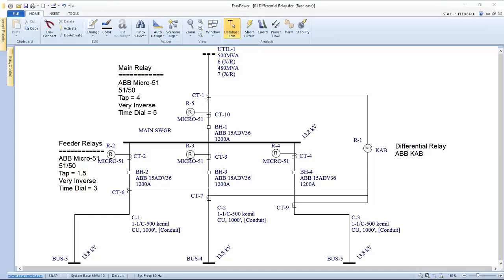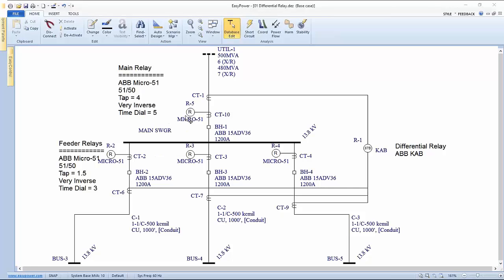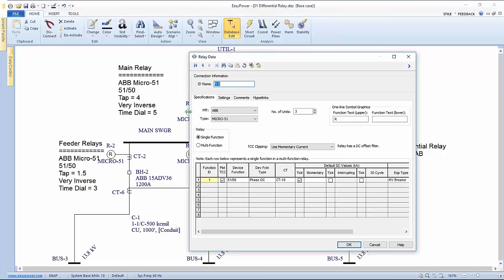Let's go ahead and jump into EasyPower and show how we're going to cover this. Here we have a kind of a typical switch gear arrangement, where we have several phase over current sensors, relays, one on the main delivery or the main input from the utility, and then one each on three of the main feeders going out of the switch gear. Each of these devices has settings that determine the phase over current trip point, and then how long time delay, how long that fault needs to be in existence before the device will trip.